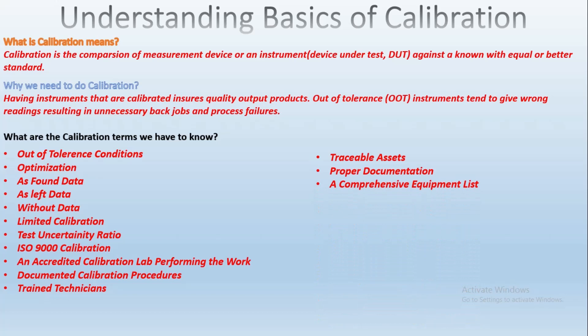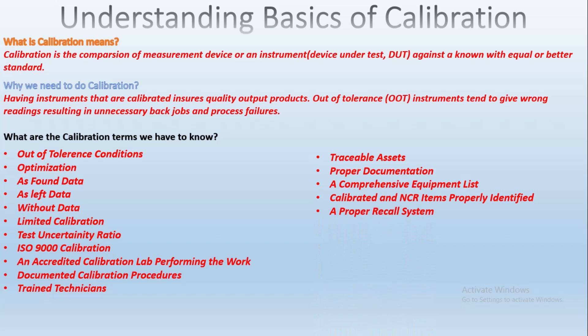The next requirement is a comprehensive equipment list. For any manufacturer to pass an ISO audit regarding calibration, they must demonstrate a comprehensive equipment list with controls covering additions, subtractions, and custodianship of equipment. The equipment list must also identify any units that do not require calibration, and controls must be in place to ensure these units are not used in any application that requires calibration.